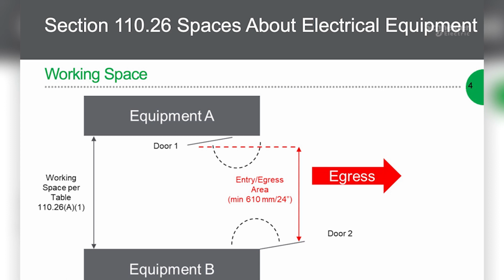When we think about an e-house or other areas like that, you may be in a really constrained location, and it's important to make sure you have that egress path. It's also important to remember that the measurement for that egress path is taken with the doors open at that minimum 90-degree angle. The code requires that doors open at least 90 degrees, so that's how we measure our egress path. Even if the equipment is capable of opening the door more than 90 degrees, that's all well and good if there are no constraints or limitations on the space where the equipment is being installed.